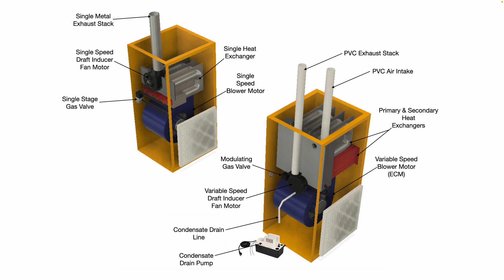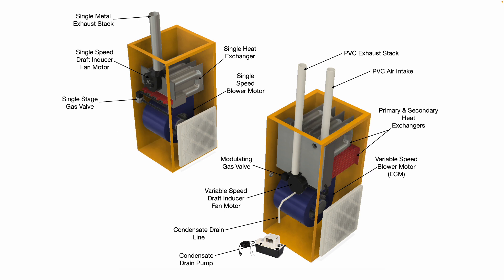That condensate drain line usually needs to go to a floor drain or to a condensate drain pump like you see here. There's a little float switch inside the condensate drain pump — when the float switch rises with the water level, it pumps the water out, and as the water level drops the float switch drops back down and shuts the pump off.